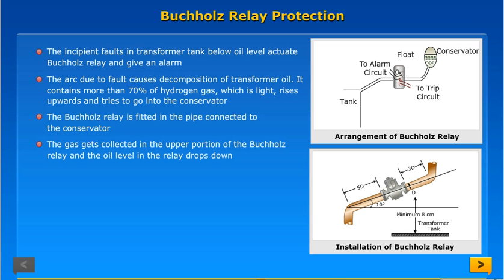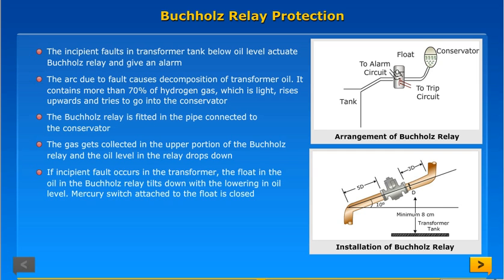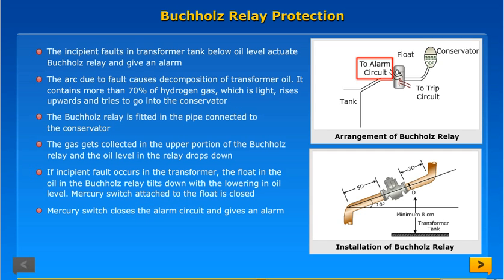The gas gets collected in the upper portion of the Buchholz relay and the oil level in the relay drops down. If an incipient fault occurs in the transformer, the float in the Buchholz relay tilts down with the lowering in oil level. The mercury switch attached to the float is then closed, completing the alarm circuit and giving an alarm.